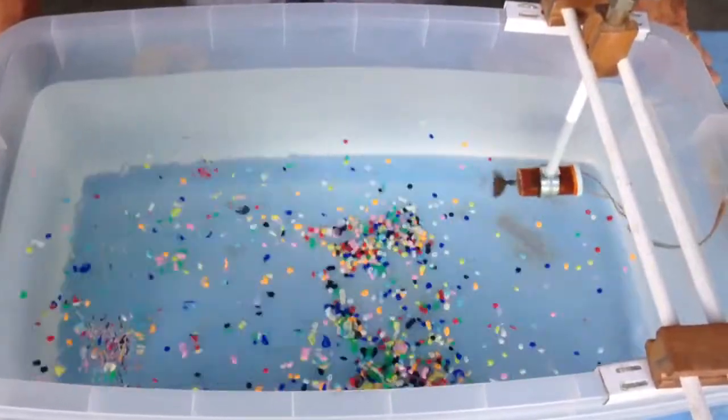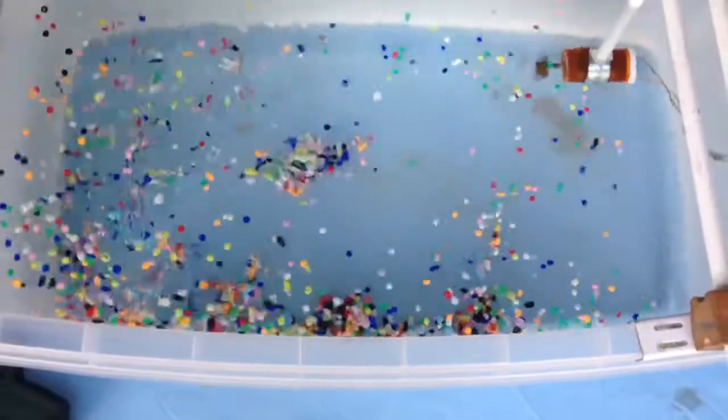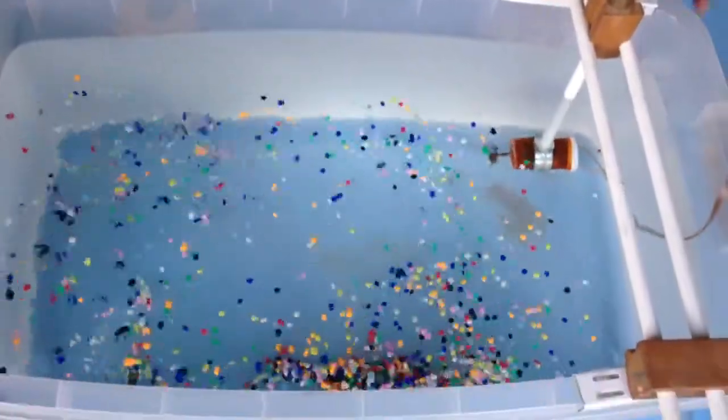You'll notice probably, as you already have, that we're going to get more of a rotational pattern like this. So there are some mixer manufacturers that this is their recommended position for the mixer, back in the corner and straight on like this. But again, we have to remember that this applies to basins with the ratio of 2.5 to 1 length to width for a single mixer.